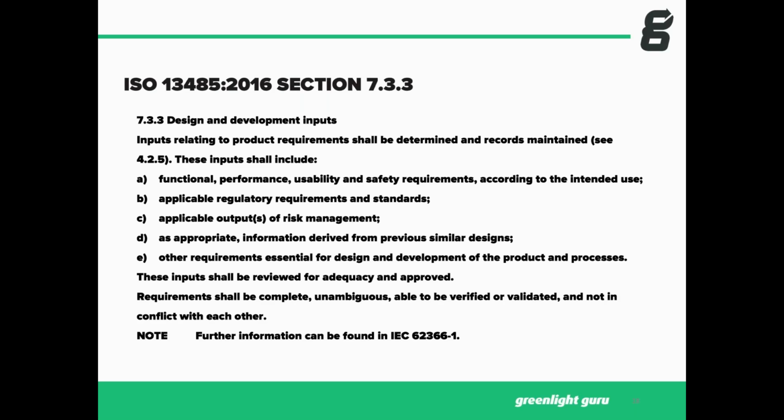ISO 13485:2016 is very, very similar to 820.30(c) when it comes to talking about design and development inputs. Again: functional, performance, usability, safety. You can see this is all articulated within the standard. Regulatory criteria, to tie into risk, that's important as well.